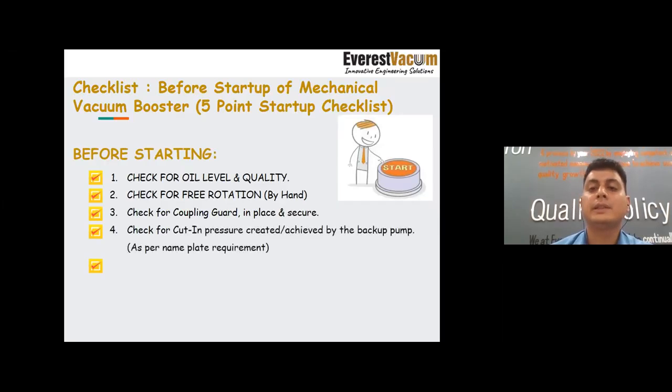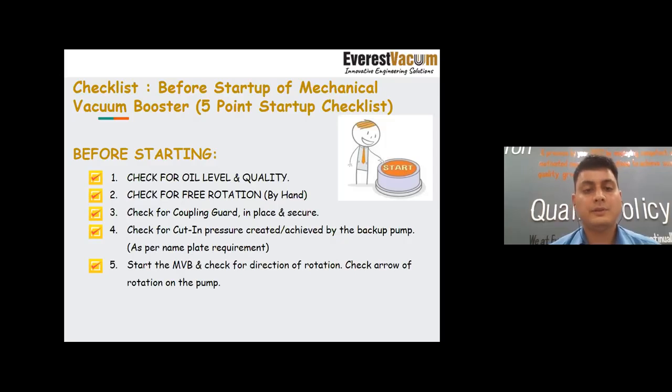Check the cut-in pressure achieved by the backup pump. As the machine name itself specifies, it is a mechanical vacuum booster. It will boost the level of vacuum created by the backup pump. So on each and every model of ours supplied into the market, we have a nameplate mounted on the machine, which clearly specifies the cut-in pressure required for the particular model. So we should be checking that, and thereafter only the machine should be started. Thereafter, we should start the MVB and check the direction of rotation, and check the arrow for the rotation on the pump. It is mounted on the machine itself.